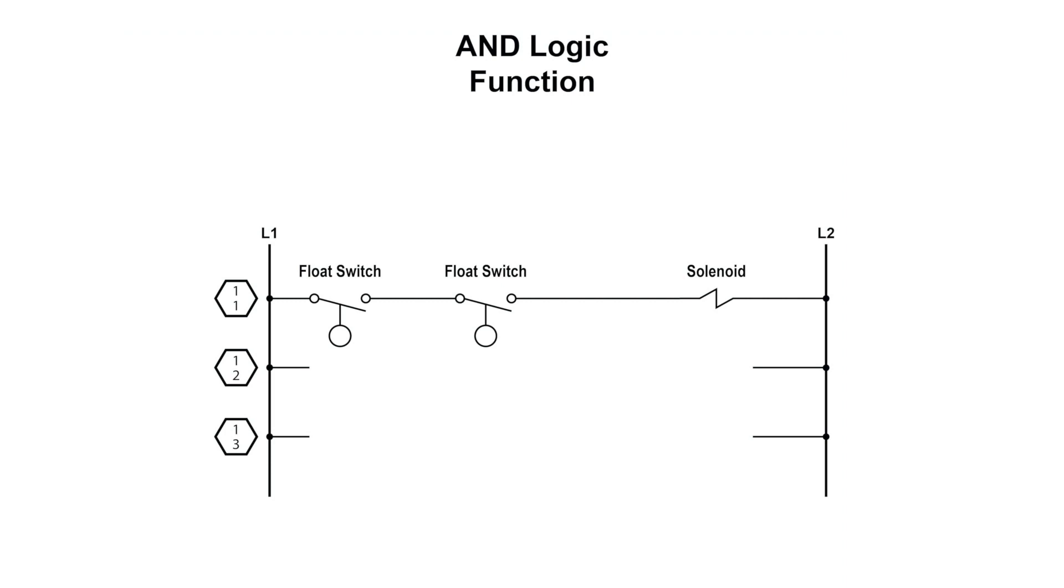The AND logic function operates like a series circuit. They are used when two or more inputs are connected in series and they all must be closed in order to energize the output. The example shows two float switches in series. Both the float switches must be closed before energizing the solenoid and performing an action such as allowing water or some type of substance to flow.